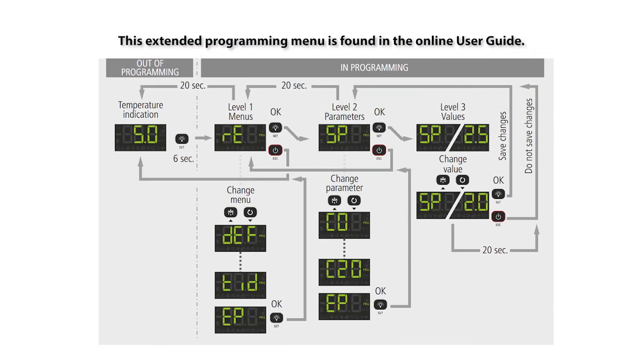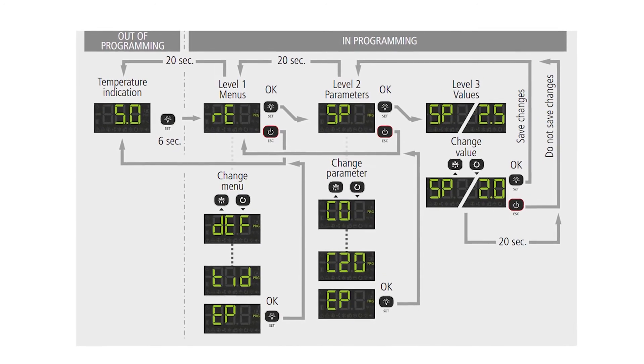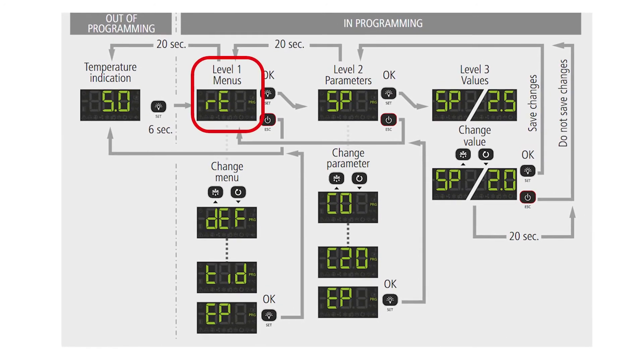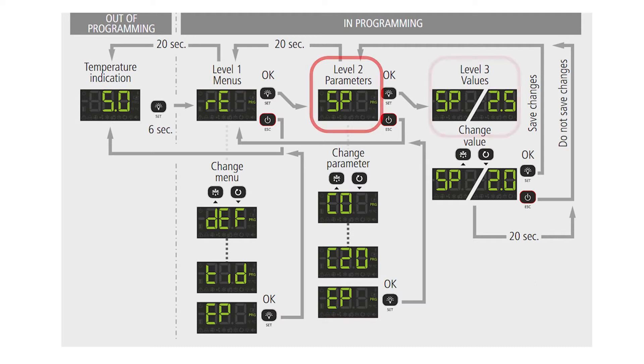Shown is the pathway for moving through and selecting values in the extended wizard parameter menu. It works on parameter levels, with level one being a process such as defrost, alarms, or regulation of control, while level two parameters will be in the level one group. So setting the maximum defrost duration would be a level two parameter in the level one defrost group. The value of the level two parameter — say 40 minutes for maximum defrost duration — is a level three parameter, and this will be what you ultimately select and set.